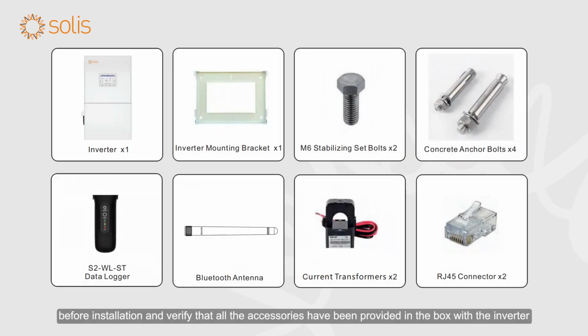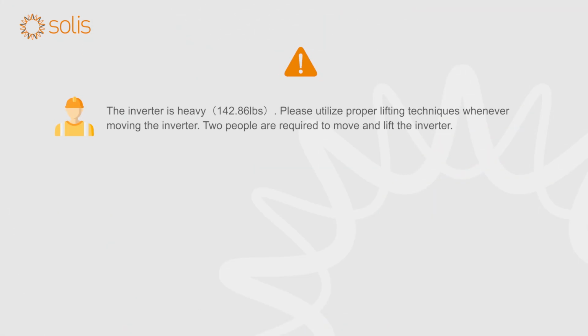Please read the full user manual before installation and verify that all the accessories have been provided in the box with the inverter. The inverter is heavy. Please utilize proper lifting techniques whenever moving the inverter. 2 people are required to move and lift the inverter.